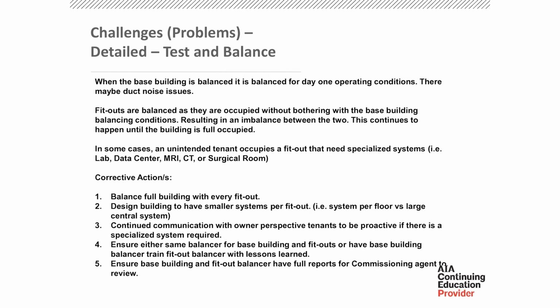When the base building is balanced, it is balanced for day one conditions. There may be duct noise issues. So whenever you balance it, it might have been balanced to meet the CFM, but the feet per minute might be wrong, and that introduces issues with duct. Fit outs are balanced as they are occupied without bothering with the base building conditions, resulting in an imbalance between the two. This continues to happen until the base building is fully occupied.